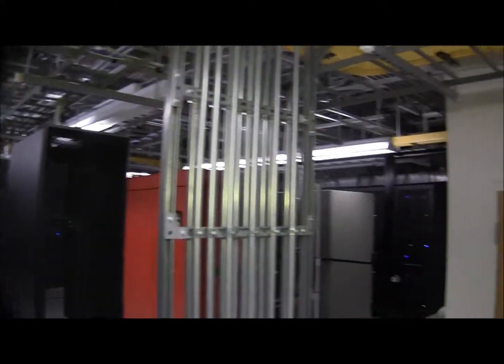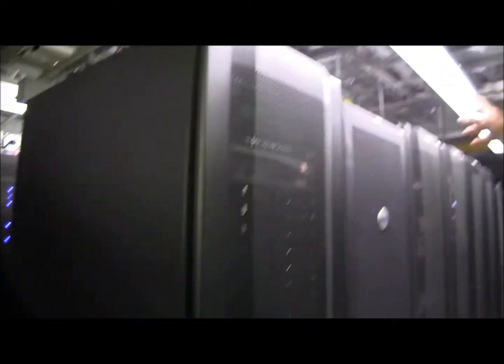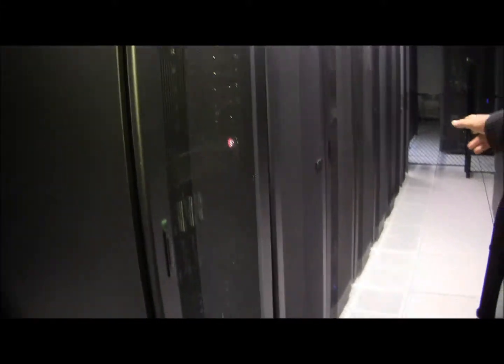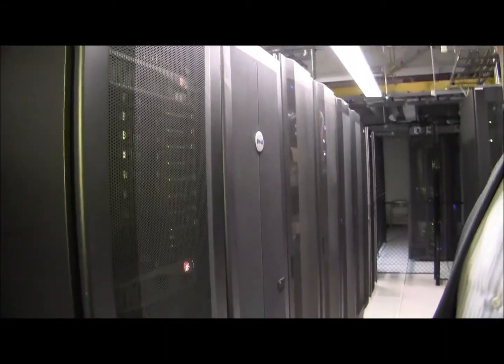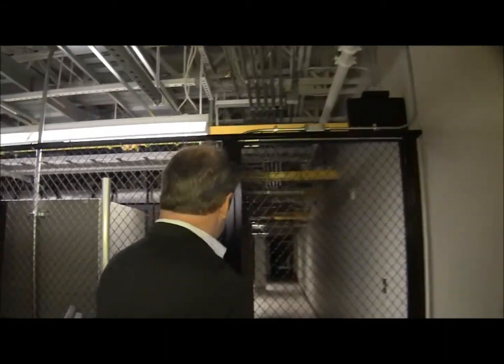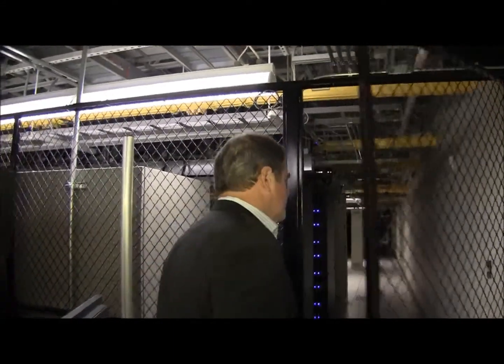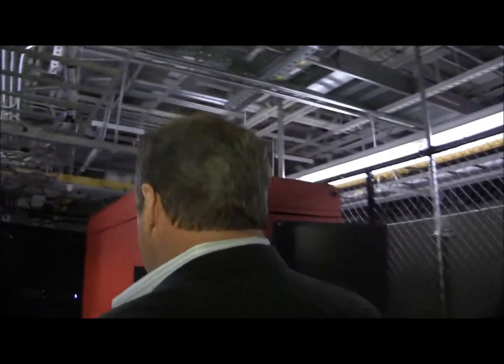This is a fairly standard configuration. Cabinet, 42U, locking, power is delivered overhead, comes in, raised floor tile, cooling tiles, hot row, cold row configuration. The data center itself is on average 68 to 71 degrees, depending on where and at what time. We utilize condenser water from 3 cooling towers that are ours. The cooling towers feed the CRAC units. The CRAC units are 2-stage. We'll have a secondary system. This is the Data Aire. That's a Liebert. The Liebert system goes out to split units on the deck to give us a 2N diversity in our cooling.